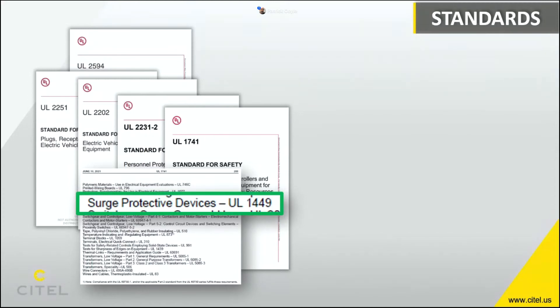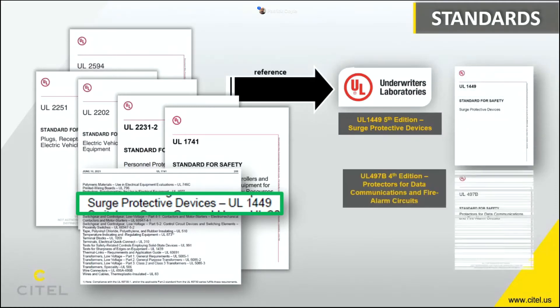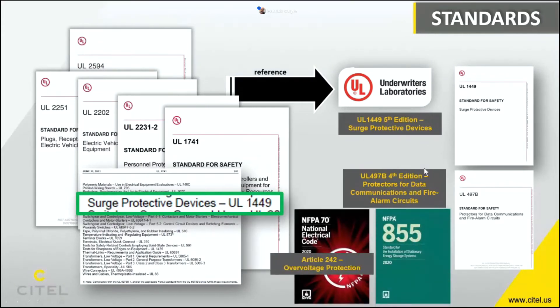UL 1449 includes production line testing plus supplements related to PV and DC power protectors. Another standard is UL 497B, with 25 sections covering signal line protectors for communication and fire alarm circuits; UL 497E for coaxial also deserves mention. These standards can be found in mandatory codes as well — notably NFPA 70, the National Electrical Code, and NFPA 855 for stationary energy storage systems.